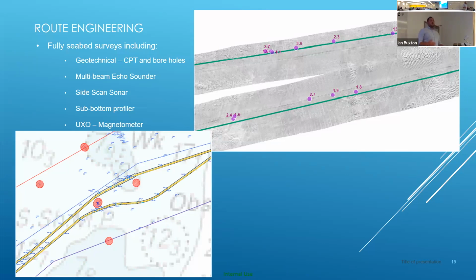Geotechnical conditions - why would we need these for a cable installation? Number one, cable thermal performance: how does the cable perform in the conditions we have on site? For example, if you have high thermal resistivity soils, such as clays, maybe a 0.7 or 0.8 TR value, that's really bad for your cable. If you have low TR value soils, such as sand, that helps dissipate heat away from the cable, so the cable's performance is improved.